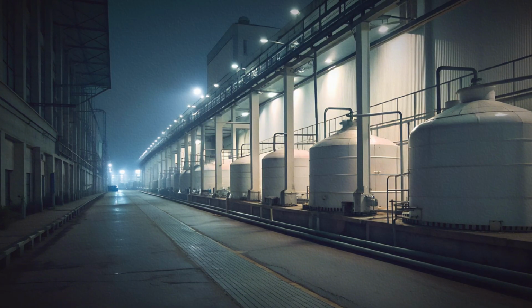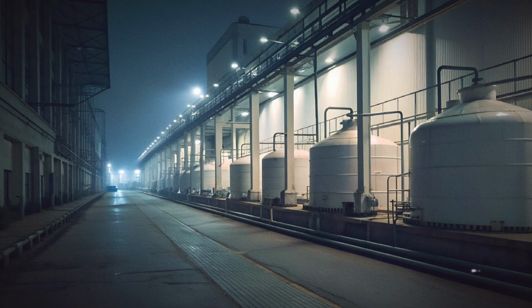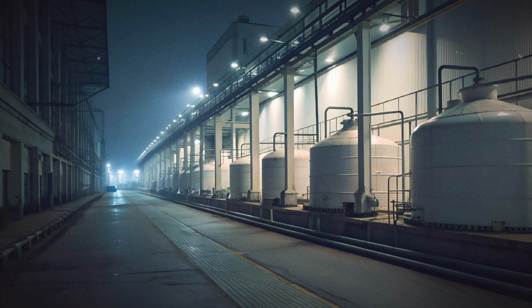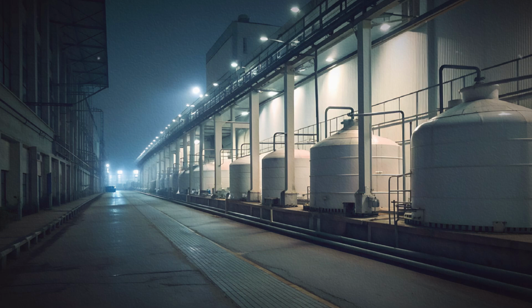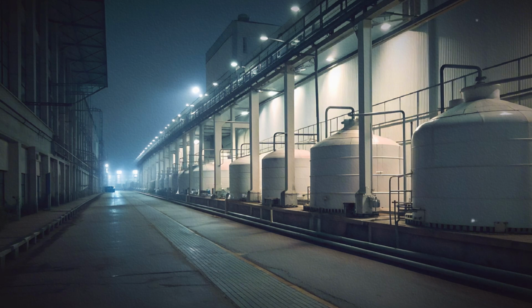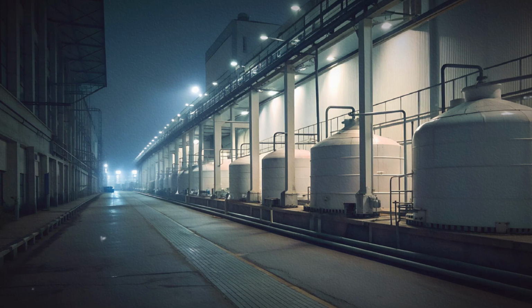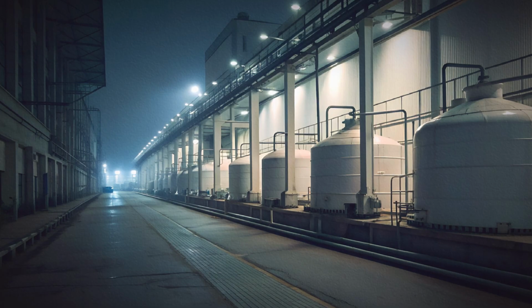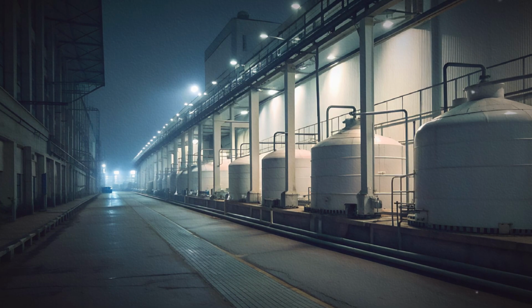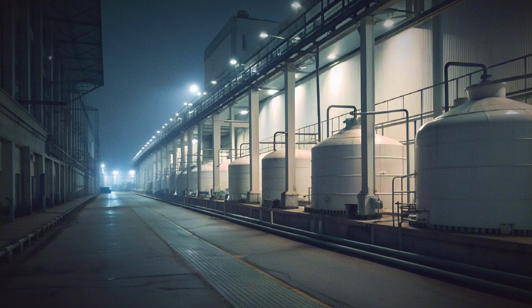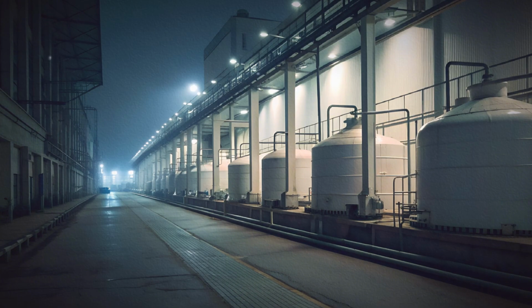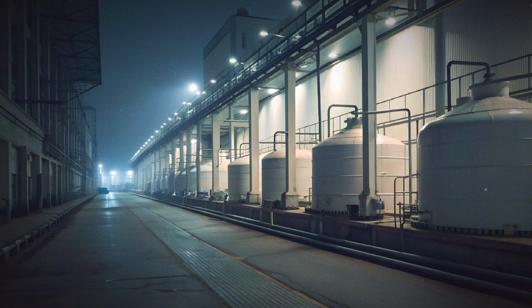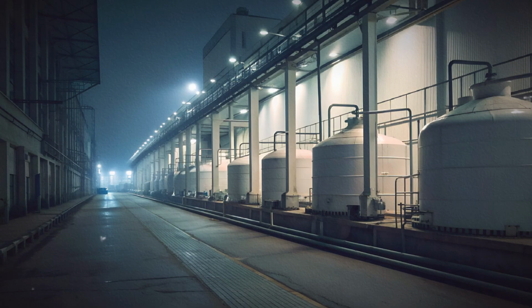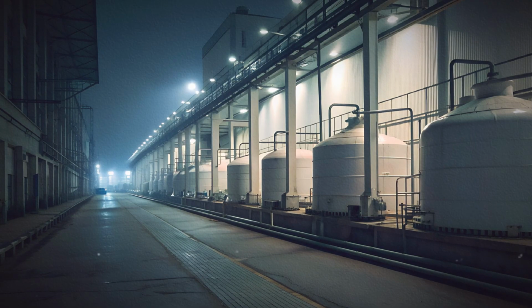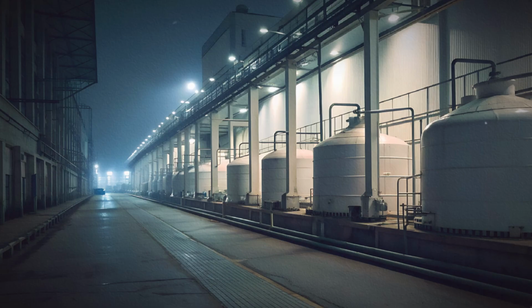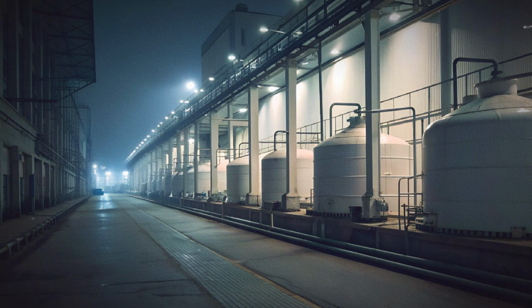Finally, filtration systems are monitored for performance and integrity. Routine sampling and laboratory analysis verify that particle removal meets specifications. Visual inspection of media condition, under-drain function and backwash clarity complements instrumentation data. When media performance declines permanently, media replacement or media reclassification may be scheduled. The goal of these practices is consistent removal of fine particles while maintaining steady hydraulic performance.